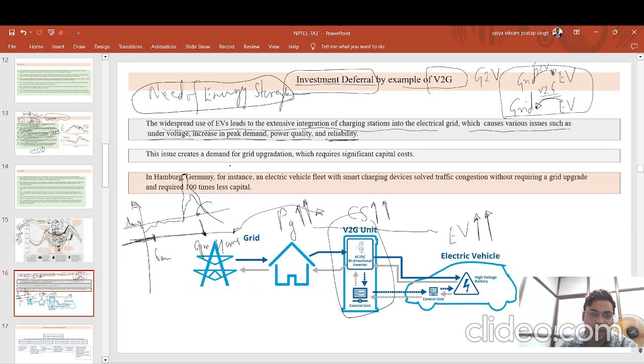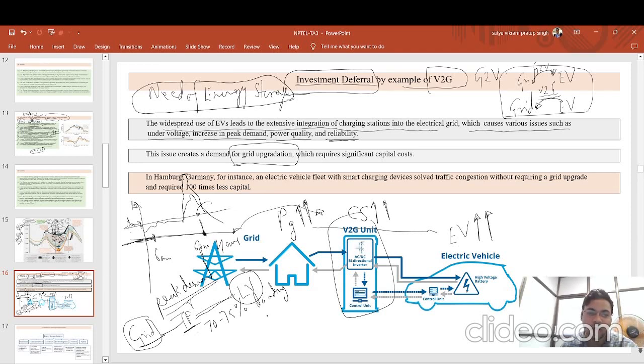That creates a huge demand for investment for grid upgradation, because this peak demand is getting increased. And who will supply this? It is supplied through your transformer itself, because if there is an LV line connected, it is connected through a transformer beforehand, before connecting to the higher power supply. This transformer has a certain loading capacity, related to 70 to 75% of its loading capacity. If you increase further with EV integration, this loading will not sustain, it will further go on increasing to 80 to 85%.